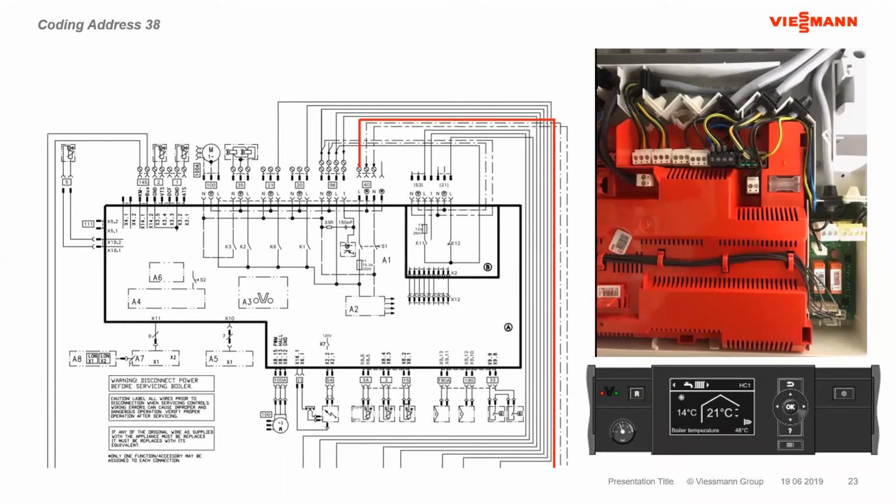So we've got the power coming in. Thanks, Mark. And he's already pushed the start button here, so we don't have to get him to do that again. So there's our 40 plug, comes down to our switch, which is already closed. And then we go through another fuse. So the control console is fuse protected like the pump module. And just so you know, there's actually a spare fuse located in that fuse holder. So there's one that's plugged into the control console, and there's a spare one you can access if you unplug that. So say you had a pump that popped a fuse, the F1 fuse down at the pump module was open because of a bad pump. You diagnose that. You actually have a spare fuse up here, so long as somebody else hasn't already used it, but it would be available there too to allow you to pop one more fuse before you got to go buy a pack of fuses.